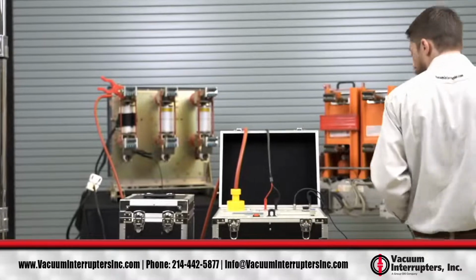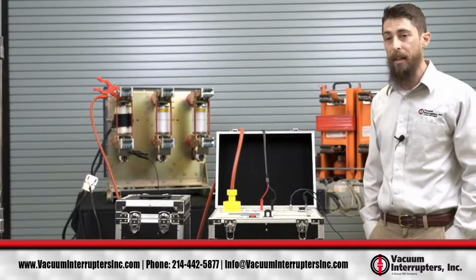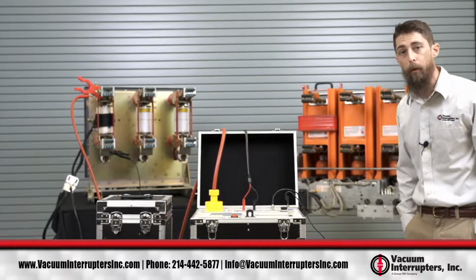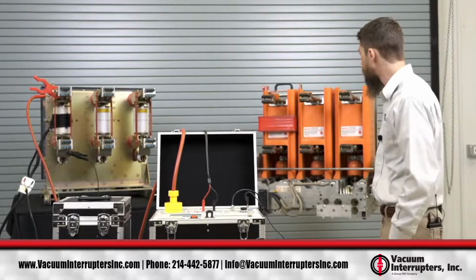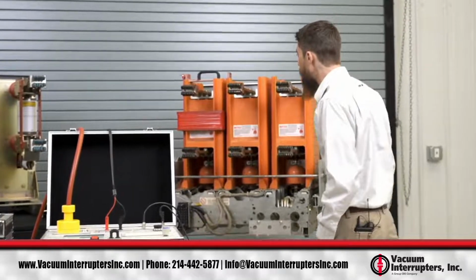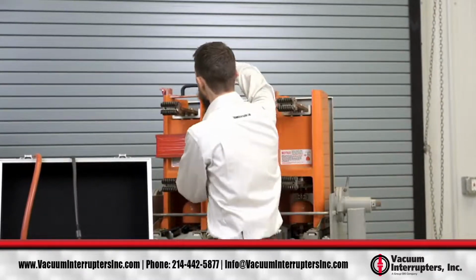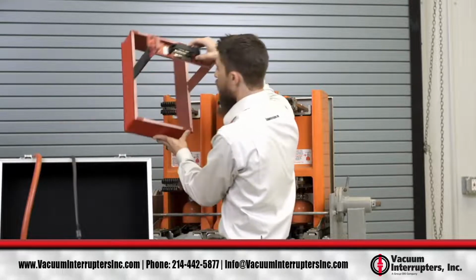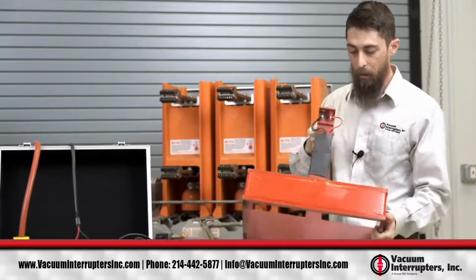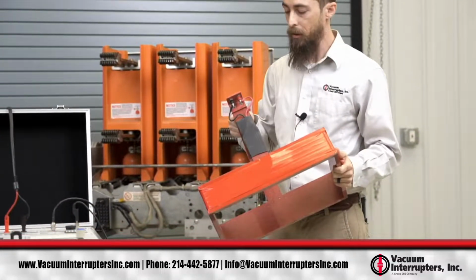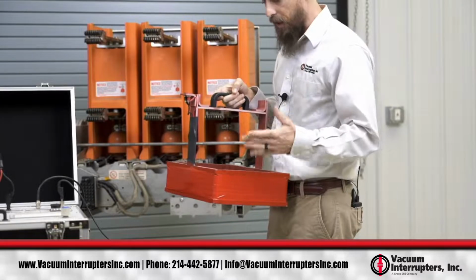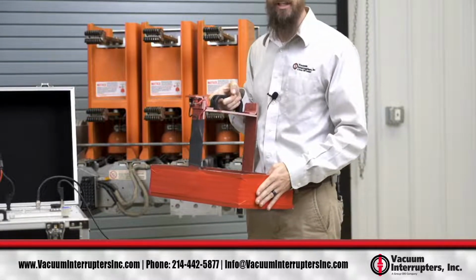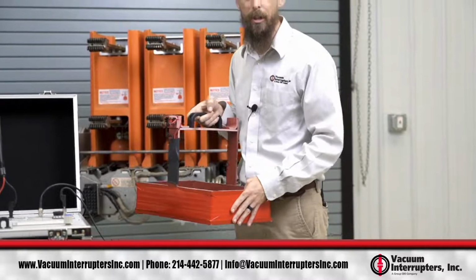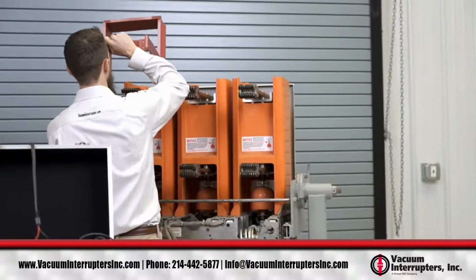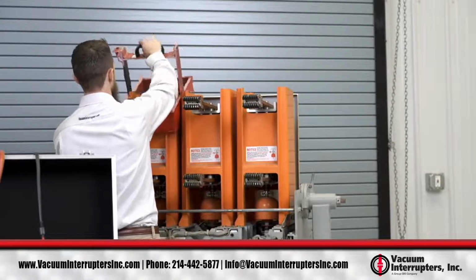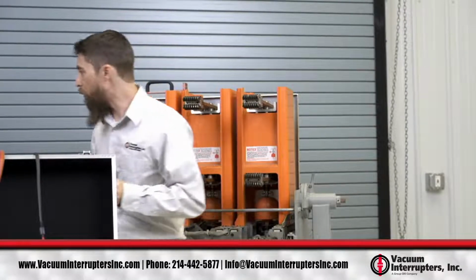So now we have some options that go with our MAC test set. So we have some custom coils for breakers that it's possible to produce a custom coil for. So we have here a GE Power Vac. So the coil, instead of being a flexible coil, is a hard wound coil with a rigid structure. We call these rigid coils. So this saves a lot of time, makes the test extremely easy. Wrapping the coil is usually the most time-consuming part of the test. So I'm going to move my cables over.